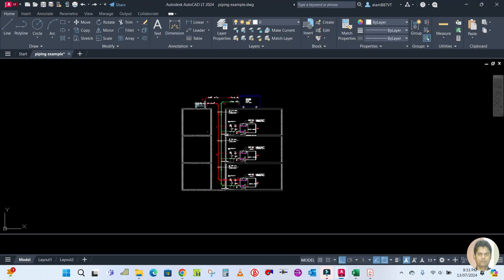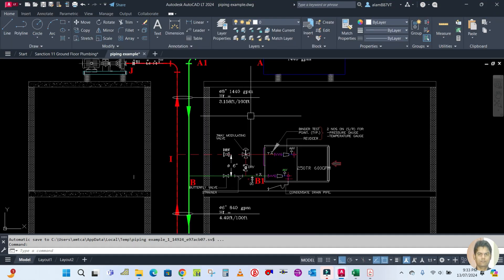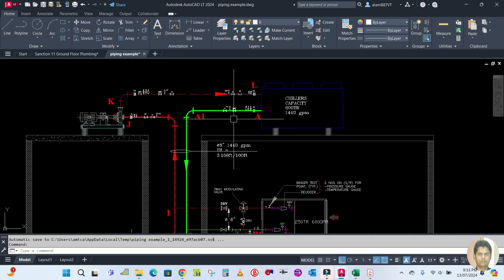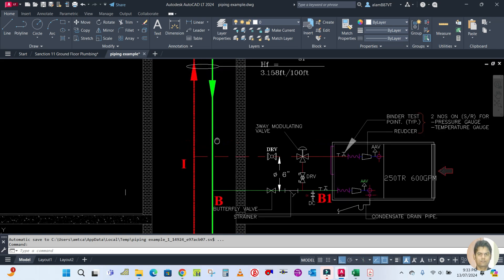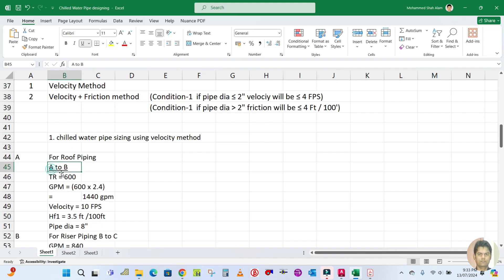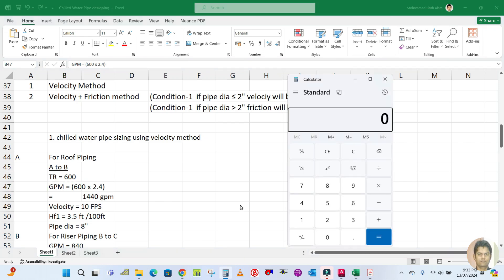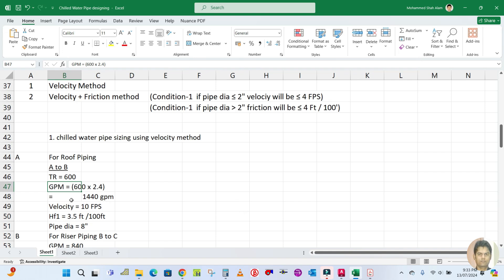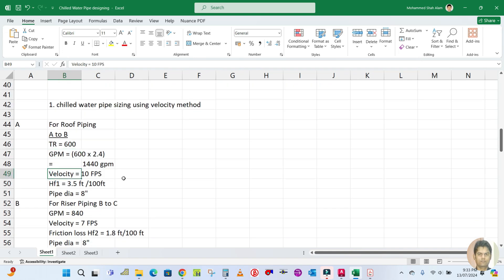Example one: we have to calculate the pipe sizing from point A to point B, which is the roof piping. The tonnage is 600. GPM equals tonnage multiplied by 2.4, so 600 into 2.4 gives us 1440 GPM. The recommended velocity for roof piping is 10 feet per second.